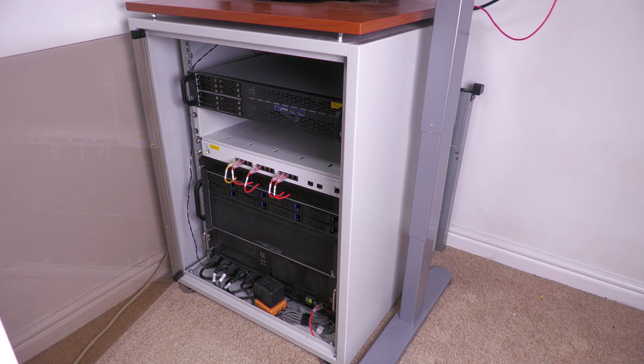So I've already mentioned that I'll be upgrading the cooling system to handle additional equipment I'll be installing. But even if I wasn't installing additional equipment, once I install the acoustic foam, I suspect I'll need to have active cooling. That's because currently, if I turn the fan off and shut the door, the rack will still dissipate quite a lot of heat through its metal walls, because metal's quite a good thermal conductor, so even though the heat inside will get quite hot, it'll dissipate out the sides.